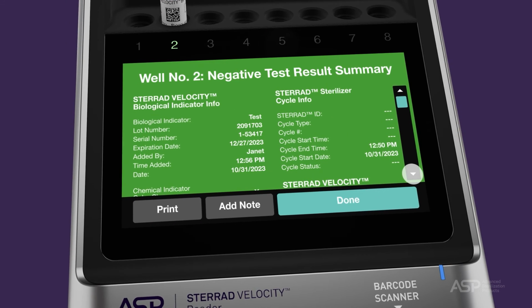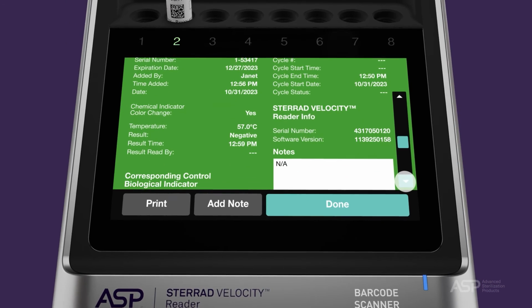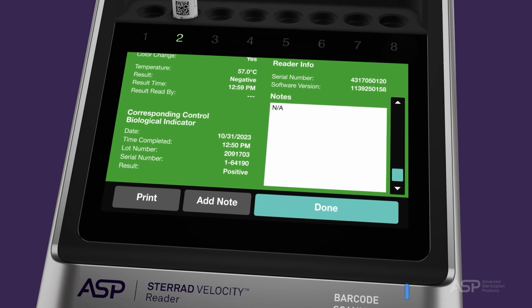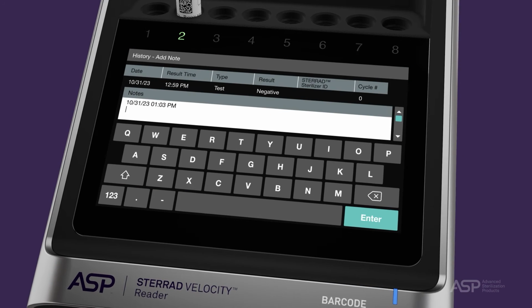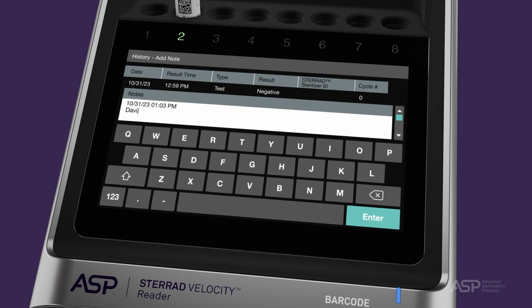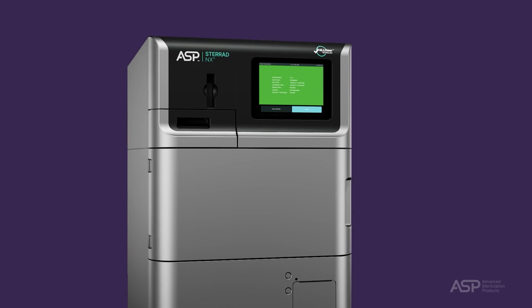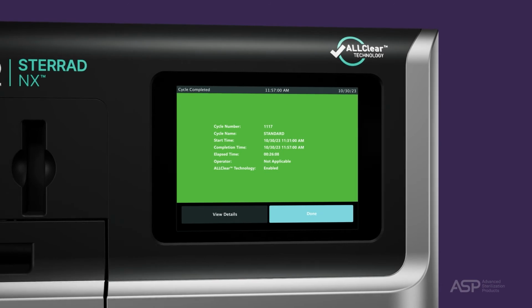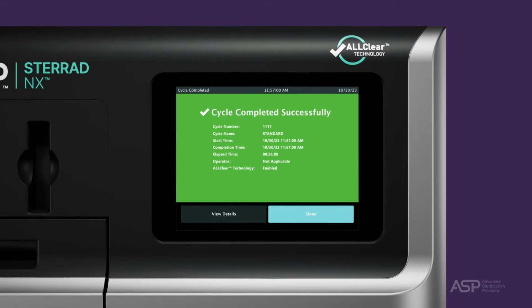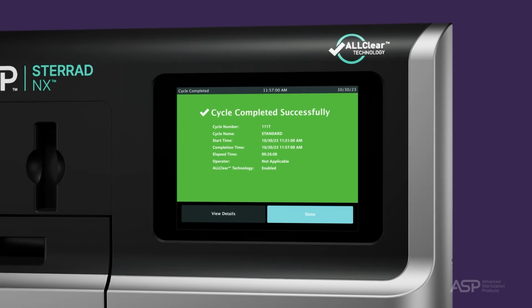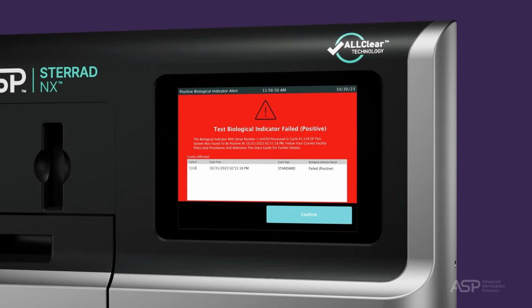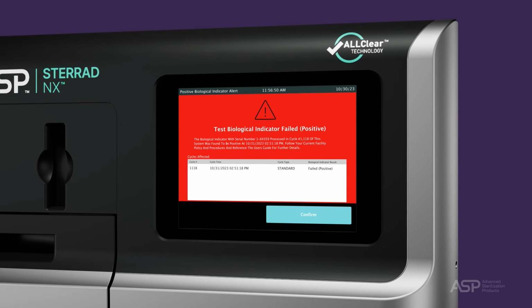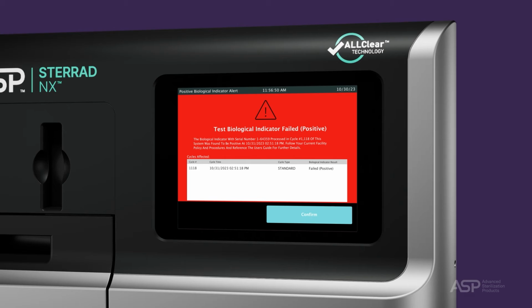For detailed information on interpretation of results, please review the instructions for use included with the biological indicator and the STERRAD Velocity Reader User's Guide. If your STERRAD system is integrated with the STERRAD Velocity Reader, the user will not be notified of negative test biological indicators. The sterilizer will be alerted when the STERRAD Velocity Reader detects a positive test biological indicator.